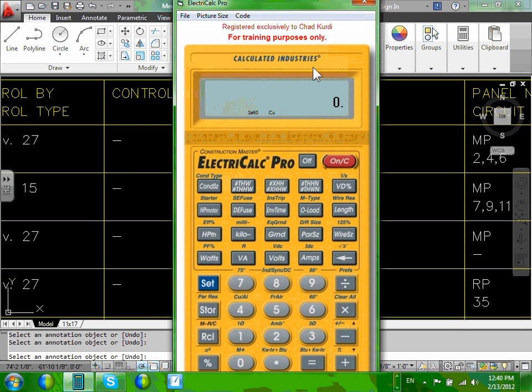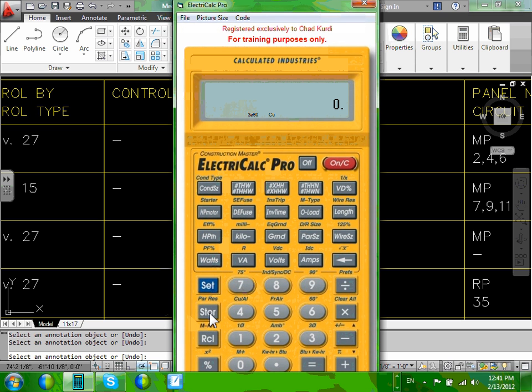fired. All right, so let's change this one to 75. I'm going copper 75, and I have 91 amps, and I need a conductor size, wire size. 91 amps, right? And I need wire size. Number 3 copper. How did you come up with the number 6? Number 3 copper. Anybody can size it other than with the calculator?